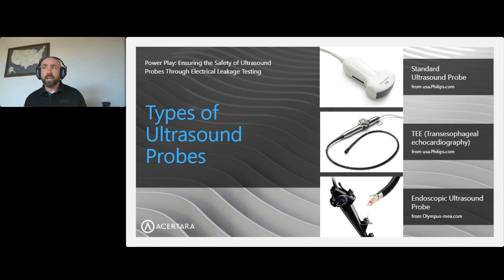So high voltage readings are not the only concern when you're looking at electric leakage. Any failure is, what are we measuring when we're actually measuring electric leakage? And this is getting a little bit ahead of myself here, but you're measuring the breakdown in the insulators between the electronics and the outside of the probe. And so that breakdown can be manifested in several ways. It can be a hole in the insertion tube. It could be a hole in the articulation sleeve or bending neck rubber. It could be a hole in the tip or a crack in the tip of the probe when we're talking about TEE probes. And that electric leakage itself can present a danger to the patient, but there are also correlated dangers that are at least as important as that particular issue.